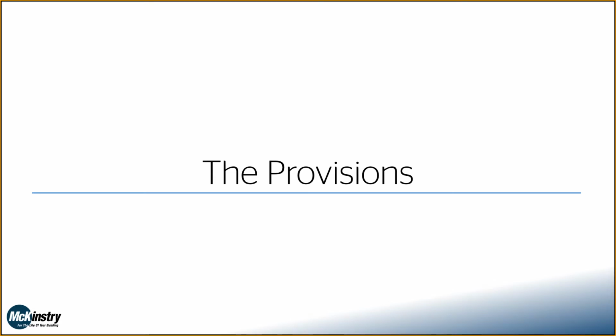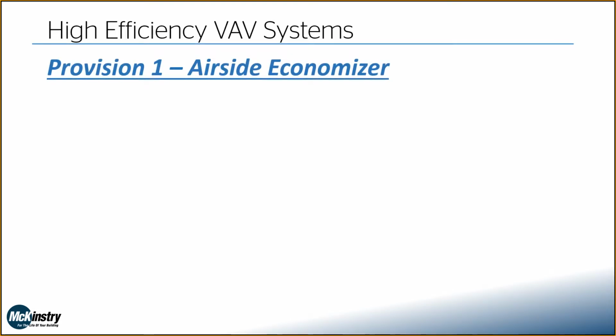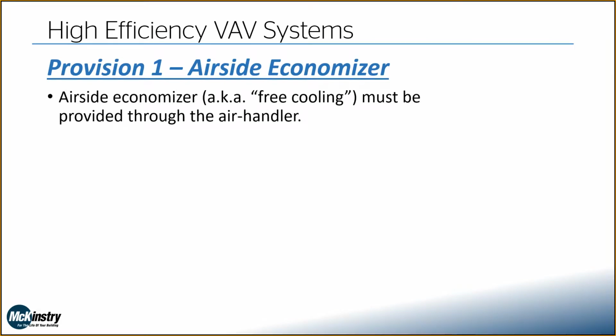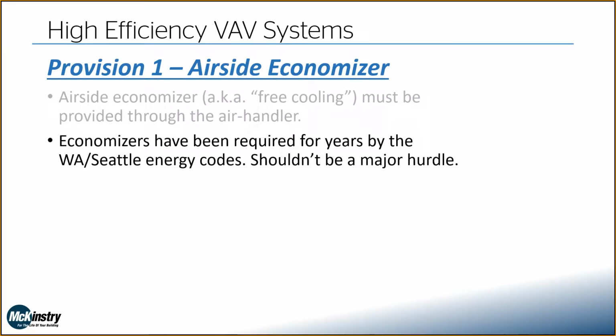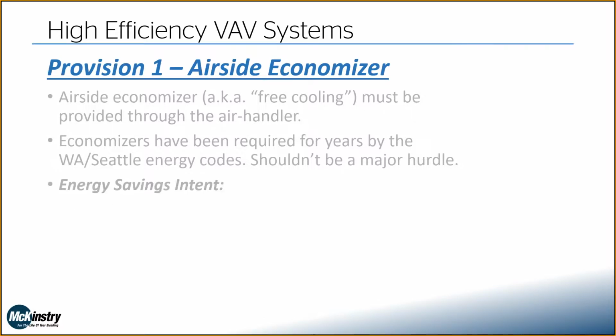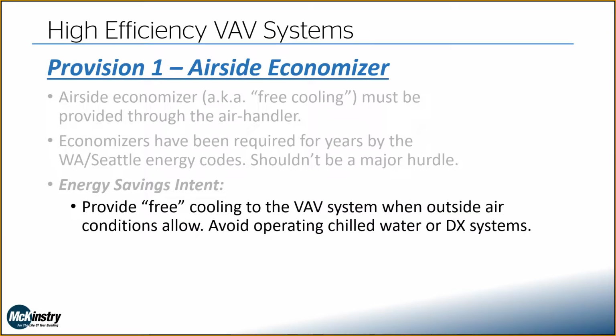All right, so let's hop into the things we have to do to be a high efficiency VAV system. The first one is pretty straightforward: an air side economizer. You have to have an air side economizer, also known as free cooling, through your air handler. We've been doing this for years and years. This should not be much of an issue, but they are saying that you have to have it. The intent here is let's provide free cooling when we can. If our outside air conditions are nice and cool, but we have a cooling load in the building, let's use that economizer. Let's avoid operating our chilled water and our DX systems.